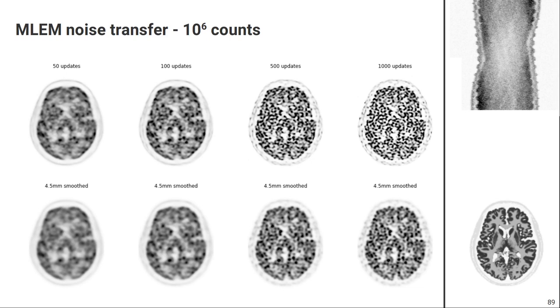If we decrease the counts even further to 10^6, there is way more noise on the measured sinogram. After 1,000 updates, close to the maximum likelihood solution, the image is very noisy and probably unusable for most clinical applications. In that case we definitely have to apply smoothing, and it also makes sense to stop the MLEM iteration early — for example, stopping after 100 updates with a bit of post-smoothing gives a more usable reconstruction than iterating long with no post-smoothing.